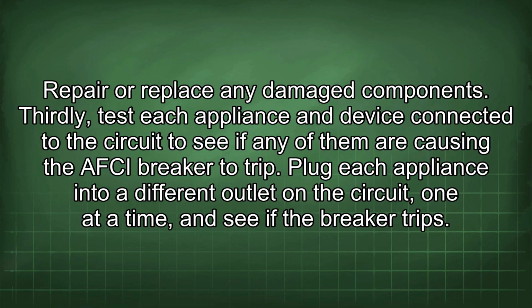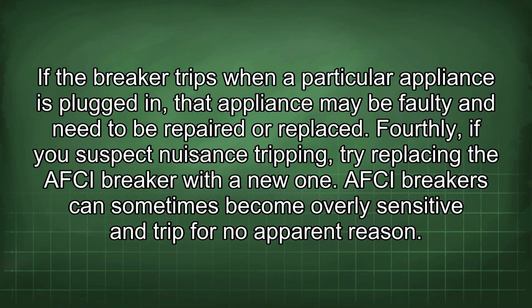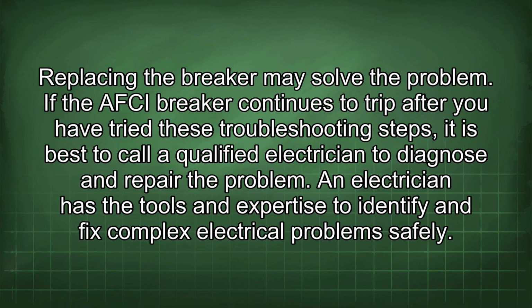Plug each appliance into a different outlet in the circuit, one at a time, and see if the breaker trips. If the breaker trips when a particular appliance is plugged in, that appliance may be faulty and need to be repaired or replaced. Fourthly, if you suspect nuisance tripping, try replacing the AFCI breaker with a new one. AFCI breakers can sometimes become overly sensitive and trip for no apparent reason. Replacing the breaker may solve the problem.